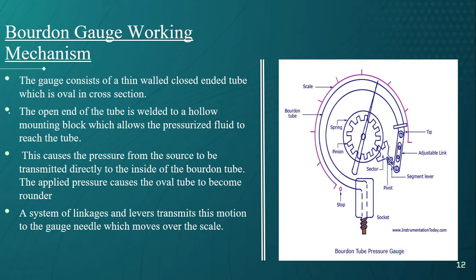In this slide we will see how a Bourdon tube pressure gauge works. The open end of the tube is welded to a hollow mounting block which allows the pressurized fluid to reach the tube. This causes the pressure from the source to be transmitted directly to the inside of the Bourdon tube. The applied pressure causes the oval tube to become rounder since a round cross section has the maximum area for a given circumference. As it becomes rounder, the Bourdon tube tends to uncurl which causes its free end to move.